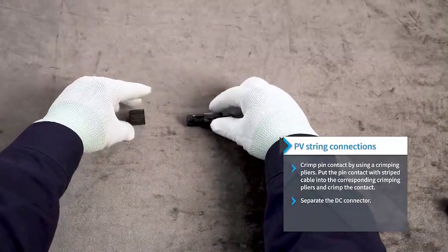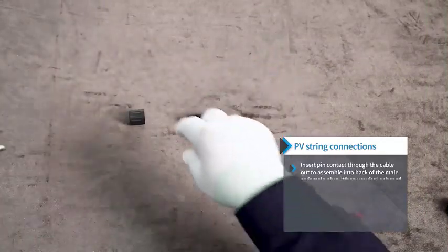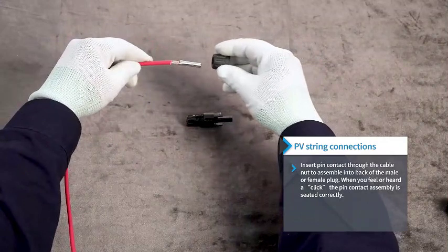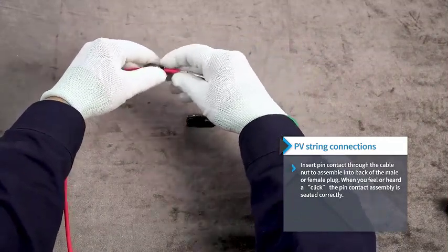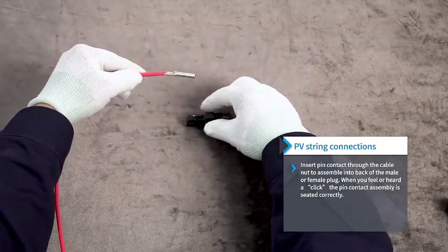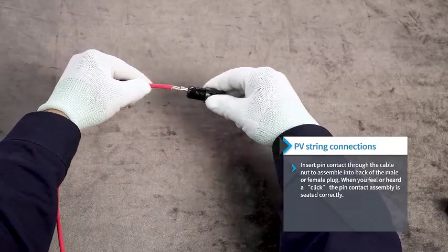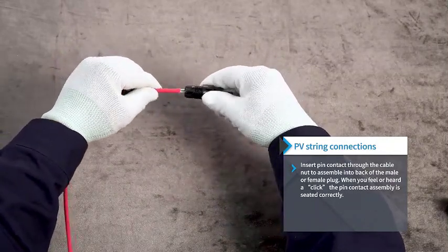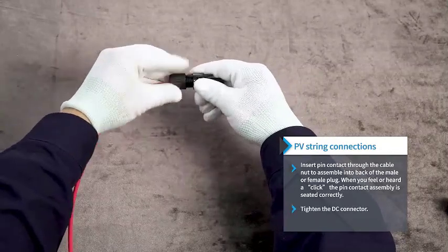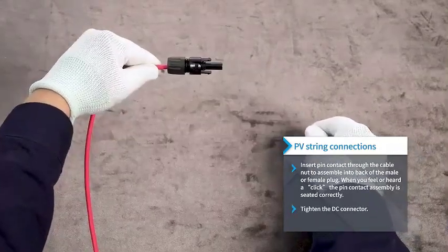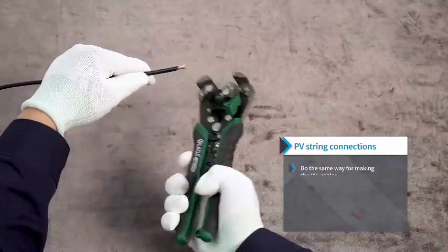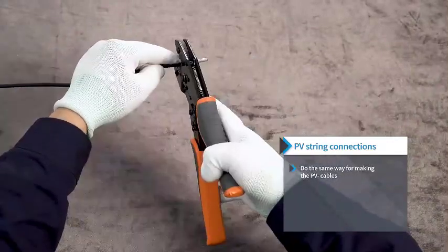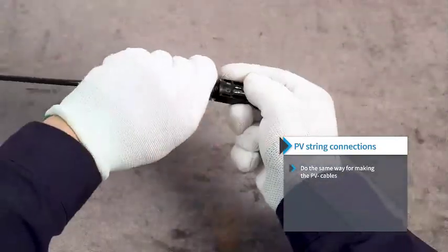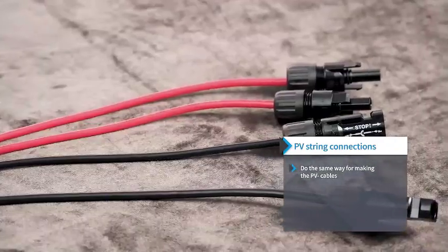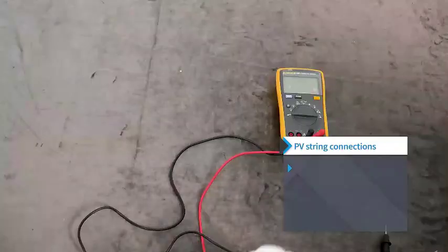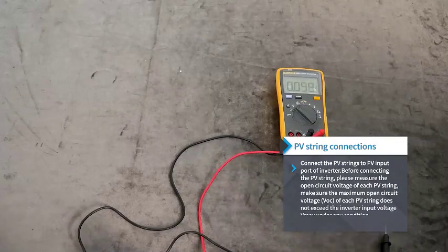Separate the DC connector. Insert the pin contact through the cable nut to assemble into the back of the male or female plug. When you feel or hear a click, the pin contact assembly is seated correctly. Tighten the DC connector. Do the same way for making the PV cables. Connect the PV strings to the PV input port of the inverter.